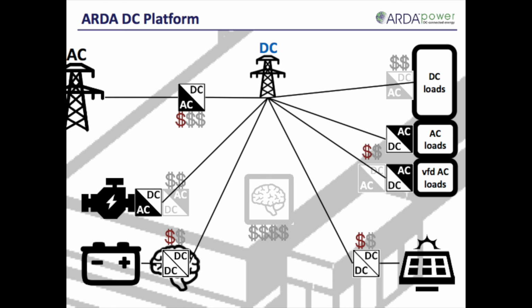Because the platform is DC and there is no need to manage frequency and phase or to worry about reactive power flows, and because the sizing of the interconnect is defined by the sizing of energy exported and imported rather than the sizing of the total microgrid storage and generation assets, the interconnect design and permitting process is much easier than for conventional systems.